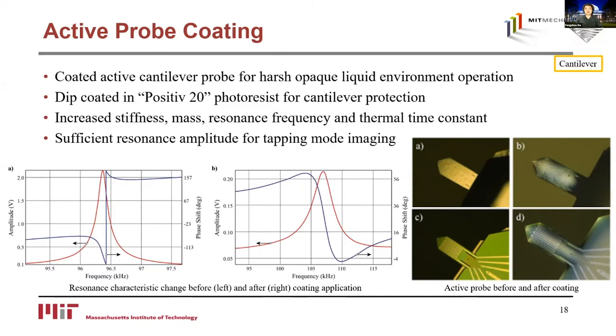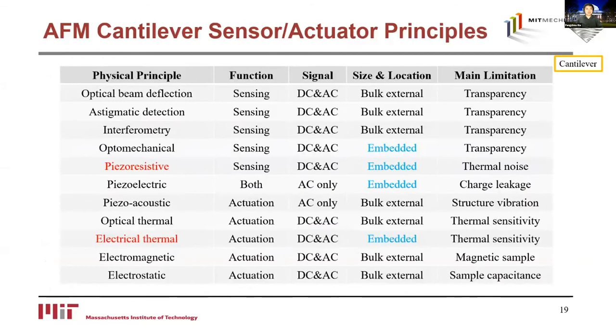There exist a number of other sensing and actuation methods for AFM micro-cantilevers using various physical principles. This table summarizes available methods based on function, signal type, size, location, and main limitation. For example, the active probe using piezoresistive sensing as well as thermo-mechanical actuation are both embedded methods but are subject to temperature sensitivity. These methods can be chosen depending on application needs. In summary, the development of cantilever probes and supporting systems enabled AFM imaging capability in chemically harsh opaque liquid environments.